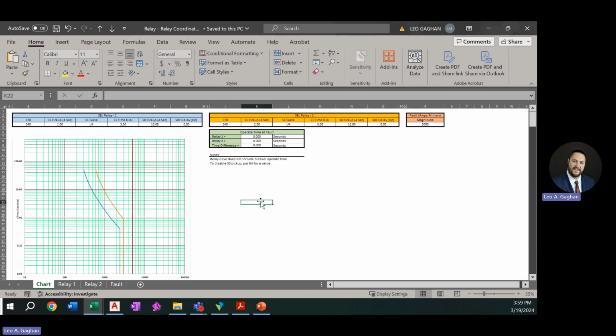These are just relay times. It doesn't include any type of breaker operation time or anything like that. And if you want to disable the 50, just put an NA in there. And the breaker operate time, those aren't in Aspen either. So this is actually consistent with Aspen that way.